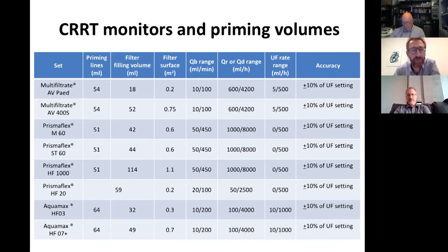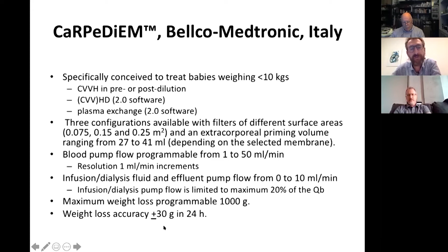That's a machine specifically conceived to treat babies weighing less than 10 kilos. We can prescribe CVVH in both pre or post dilution, or we can prescribe CVVHD. We have 3 configurations available with filters of different surface areas ranging from 0.075 to 0.25 square meters, and an extracorporeal priming volume that is quite low, between 27 and 41 ml. We have a maximum programmable weight loss of 1 kilo, and a significant weight loss accuracy set at plus or minus 30 grams in 24 hours. The control of the ultrafiltration in the Carpe Diem is quite complex. It's based on a dynamic system, and these data have been demonstrated using both in vitro and in vivo testing.